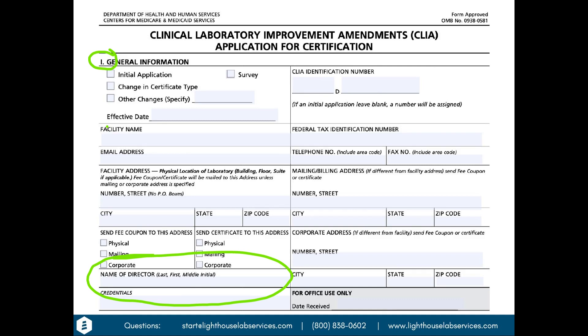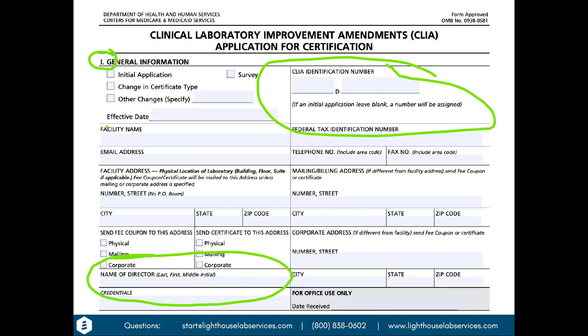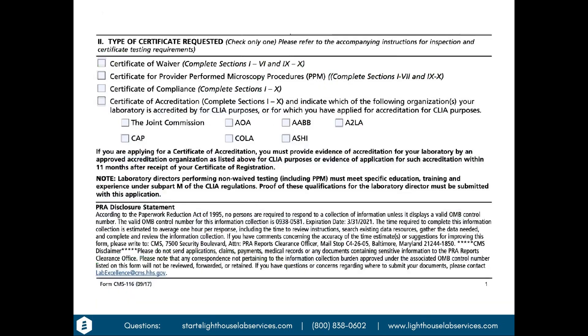One other thing to note: the form will ask for your CLIA number. You will not have one — this is your initial application, and it will be issued to you upon approval. If you are making a change to an existing lab, you would include your CLIA identification number there.